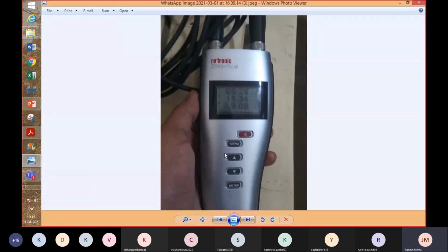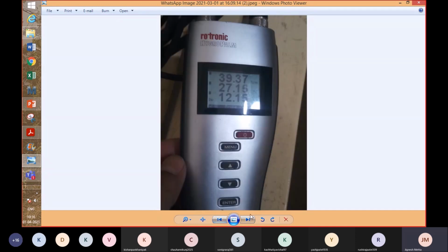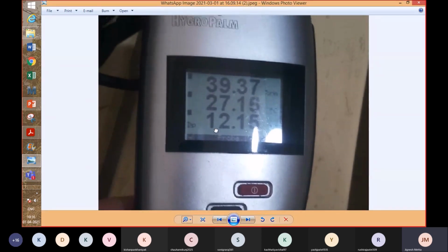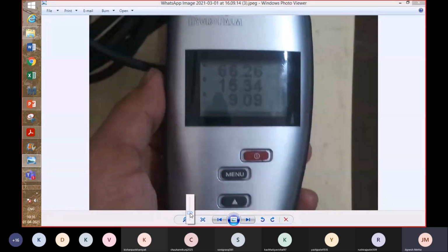So just to make you recall that, I have put these photos here. As you could see, at that time the return air condition was 27 degrees Celsius and around 39% relative humidity. So that's the condition of the air in the room, which is the entry condition for the cooling coil. And after that it is processed in the coil. And what is the condition at the outlet of the coil? It was around 15 degrees Celsius and 66% RH.